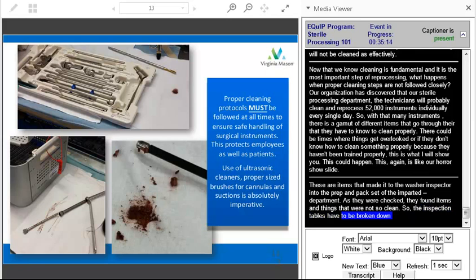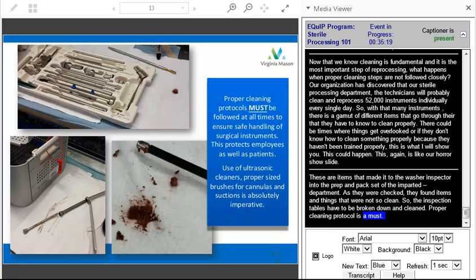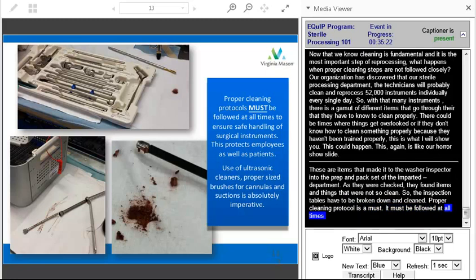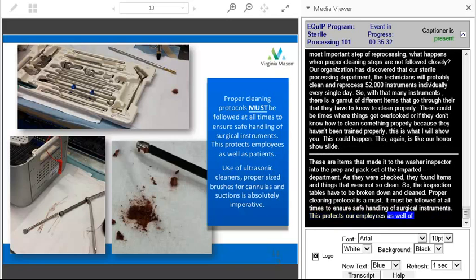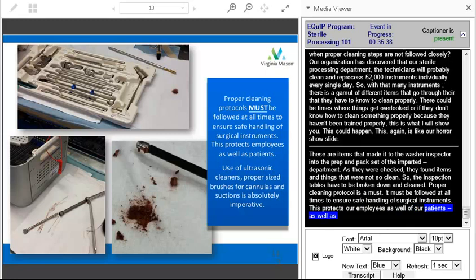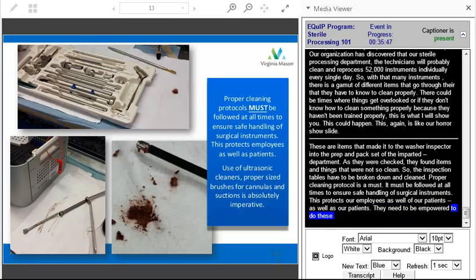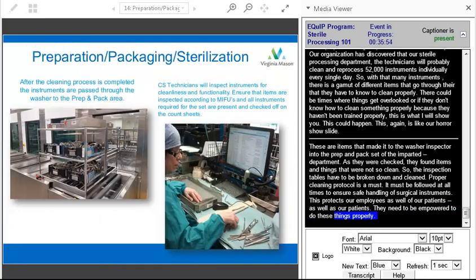So proper cleaning protocols must be followed at all times to ensure safe handling of surgical instruments. Of course this protects our employees as well as our patients. So the use of ultrasonic cleaners, proper size brushes for the cannulas and suctions, it's absolutely imperative that our technicians are empowered and they know if I have a lumen, if I have a cannula, suctions, I'm going to use a proper size brush. I'm going to flush those items. I'm going to rinse those items properly. I'm going to ensure that there's no bioburden before I put that into a washer decontaminator.